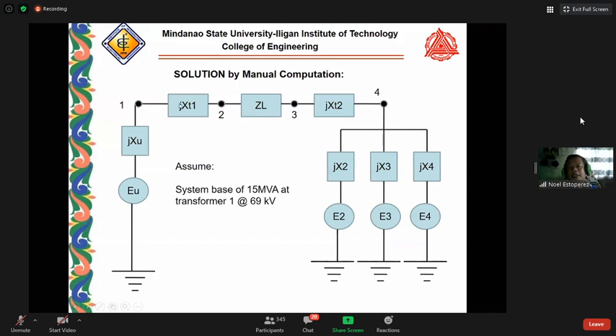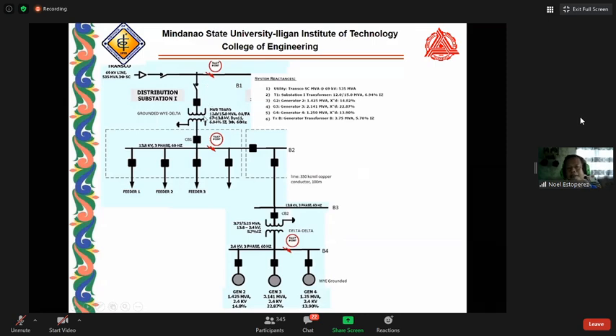our entry point here is the transformer. This represents the 69 to 13.8 kV transformer. Then a certain impedance on the line, and we have another transformer reactance here. This is from 13.8 to 2.4 kV, and the three machines or loads, motor loads, that are considered here. So this is what we are looking at from 69 to 13.8. Then we go here, it has a line with a certain conductor size, and of course its load at 2.4 kV are motors.